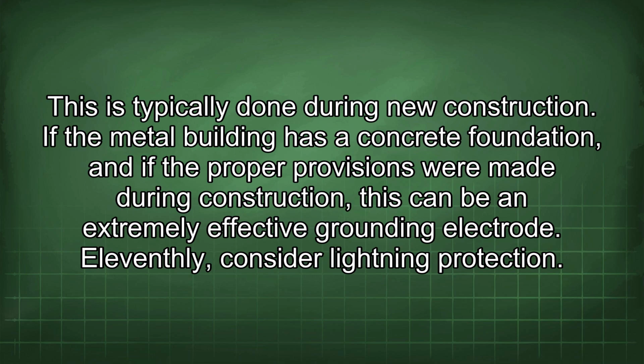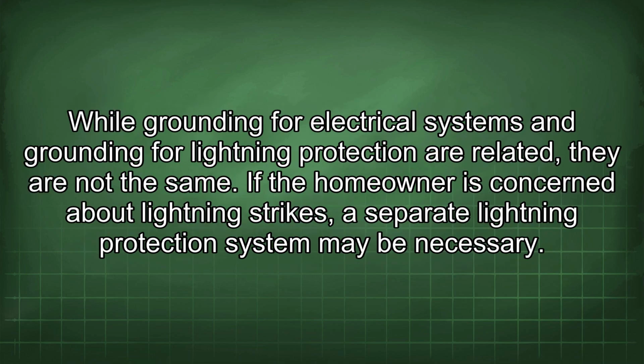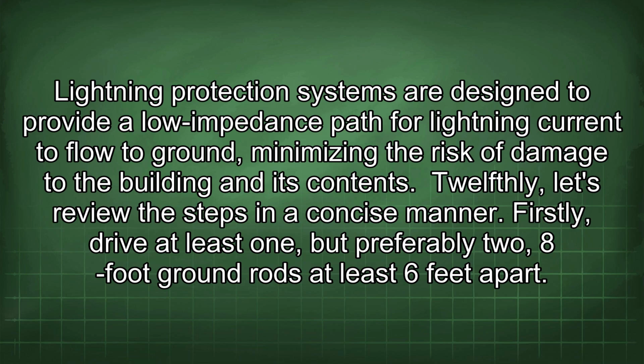11thly, consider lightning protection. While grounding for electrical systems and grounding for lightning protection are related, they are not the same. If the homeowner is concerned about lightning strikes, a separate lightning protection system may be necessary. Lightning protection systems are designed to provide a low impedance path for lightning current to flow to ground, minimizing the risk of damage to the building and its contents.